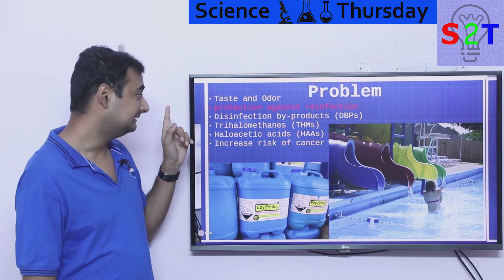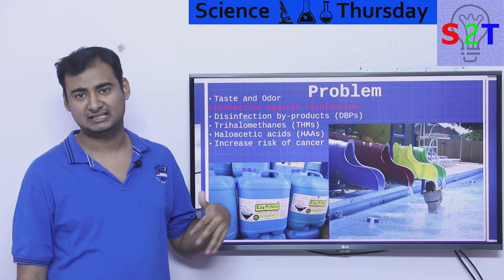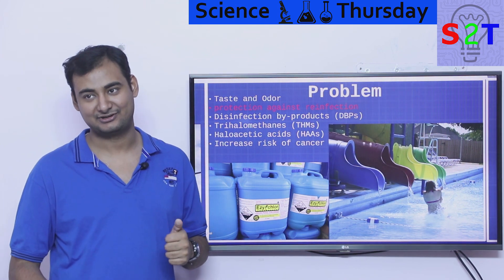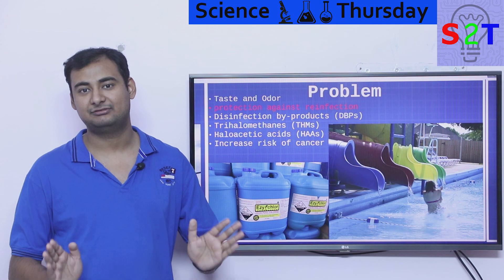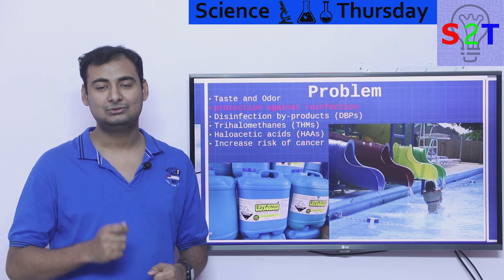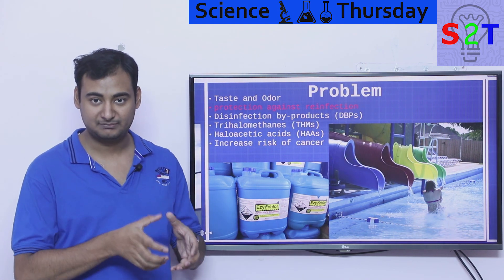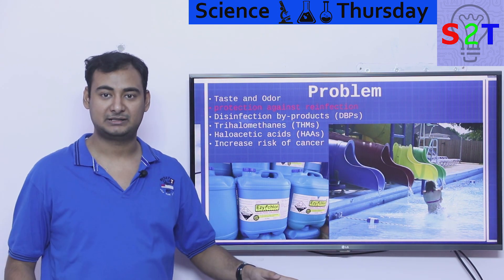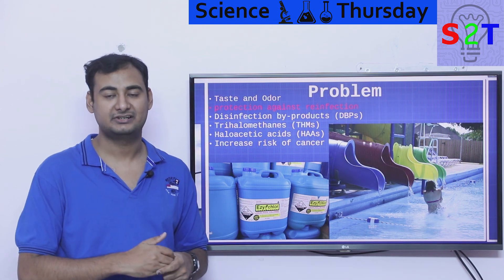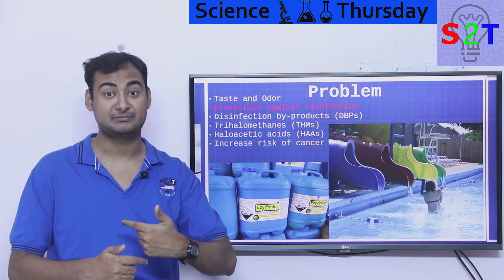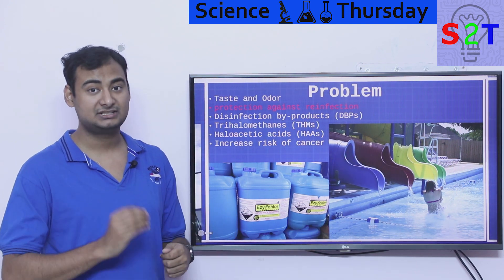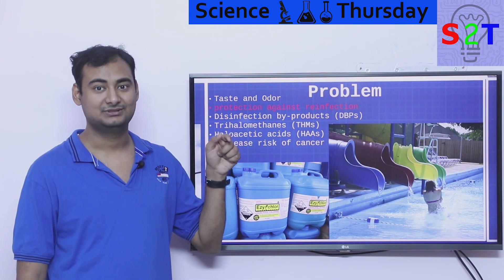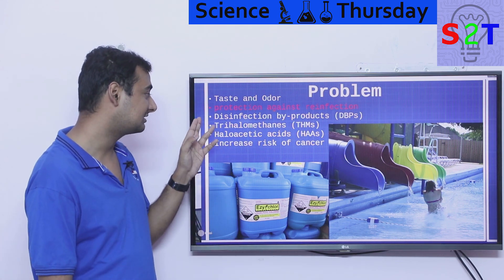Another issue, which I've highlighted as a problem, is that chlorine protects against reinfection. To do this, chlorine is re-added after the filtration process — after the water is already clean and safe — so it can protect against contamination during the plumbing system. If you have a city water treatment plant with 500–600 kilometers of pipeline, you must ensure it doesn't get recontaminated. Adding chlorine ensures bacteria and viruses cannot enter. The problem is that this active chlorine in the distribution system produces disinfection byproducts, or DBPs.